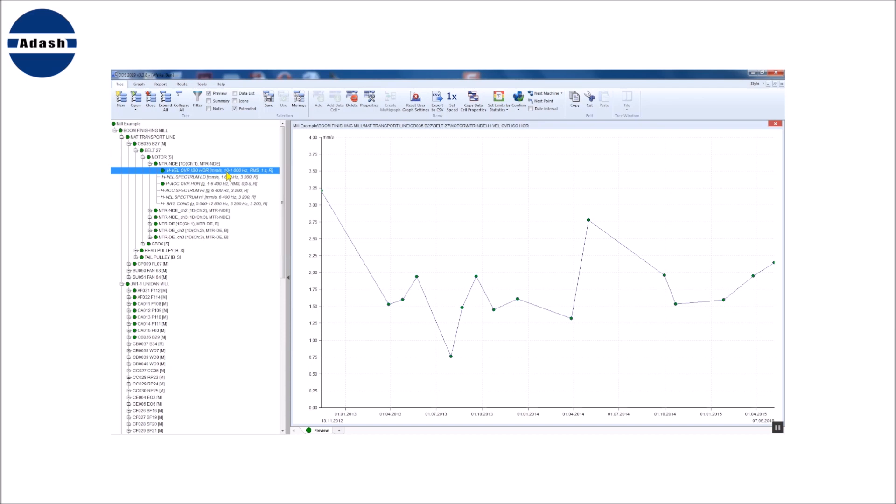Selected data cell has to contain some good condition data. It means measurements which were taken when the machine was in good condition. Now I select the limits by statistics function and all cells together option.